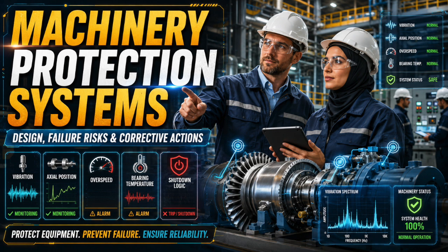But two things must be true. First, the probes must be located where the movement matters. Second, the shaft target surface must be suitable for measurement. A proximity probe does not magically know the difference between true vibration and bad target condition. If the shaft surface has mechanical runout, electrical runout, marks, discontinuities, plating issues, magnetic variation, or poor finish, the probe can produce a signal that looks like vibration but is not true vibration. And if you simply accept that reading without questioning the measurement chain, you may alarm unnecessarily, trip unnecessarily, or worse, miss the real problem because you have lost confidence in the system.